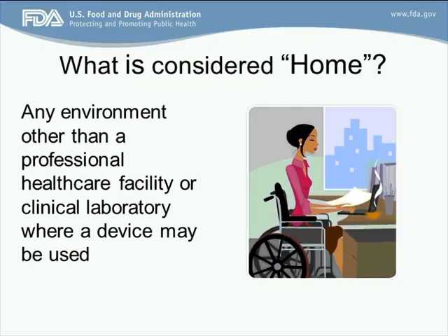If the device is intended to be used in both a clinical facility and in the home, then it will be considered a home use device, so it will need to be labeled as such.